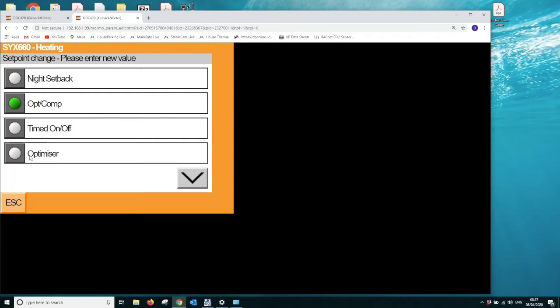Optimizer only, which is the bottom option on this particular page, this allows us to drive the pump output from an optimizer start perspective. There is no other temperature control functions with this. It's purely an optimized start function. The output will remain on for the remainder of the day, and it will optimum off. There is no additional boiler control. The hot water menu still remains active, but it doesn't sequence the boilers, and it doesn't provide any variable temperature control.